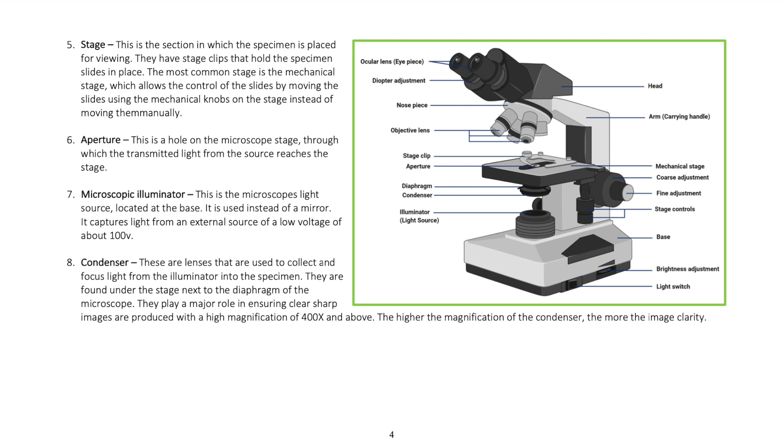The condenser consists of lenses that are used to collect and focus light from the illuminator into the specimen. They are found under the stage next to the diaphragm of the microscope. They play a major role in ensuring clear, sharp images are produced with a high magnification of 400 times and above. The higher the magnification of the condenser, the more the image clarity.